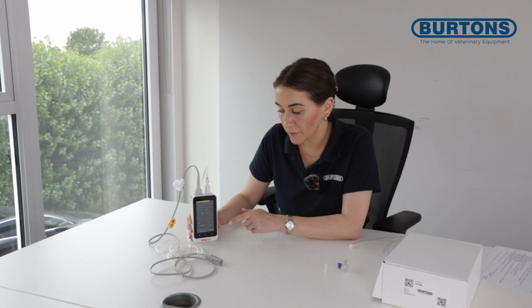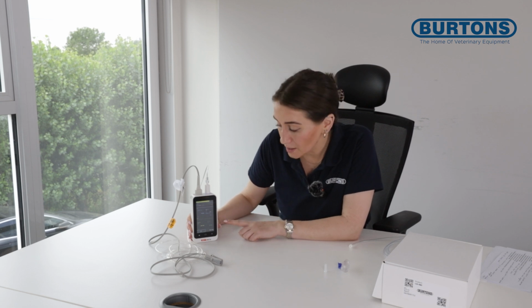So now that we've turned our machine on, we've connected our filter, our sample line and our SPO2 probe. The first thing that we'll want to do is select our species. This machine can monitor dogs, cats and horses, and the selection of the species will alter the alarms that the machine will give.